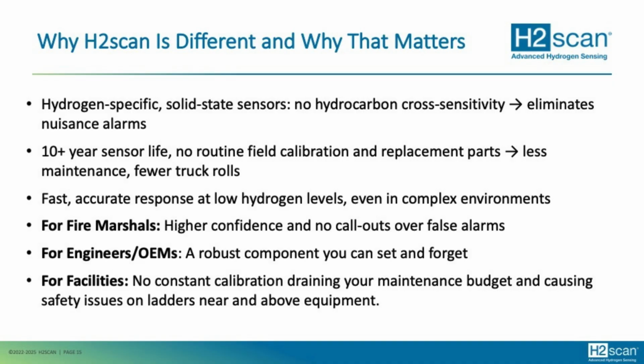And for facilities, there's nothing draining your maintenance budget or creating an unsafe situation where maybe personnel have to get up on ladders or lifts, or have to maintain sensors that are high on the ceiling, causing safety issues with OSHA. I actually came across a facility the other day where OSHA said that the way they were trying to maintain their sensors, by standing on very tall A-frame ladders without fall risk, they couldn't do it. So they had to basically shut the sensors off and buy sensors that had automatic calibration, as well as no maintenance and no replacement parts. And so that solved their problem with having an unsafe environment, with them crawling on ladders with hydrogen calibration bottles and trying to do maintenance throughout the year. So we've solved all these issues for the industry.